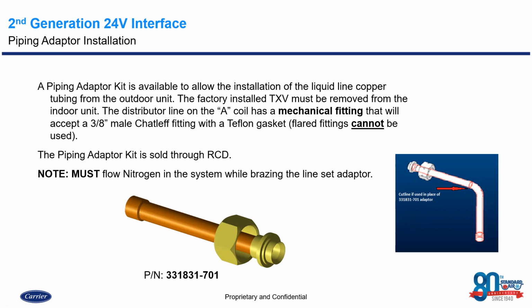Okay, brazing is allowed with this particular joint, and it kind of goes against everything that we've known with ductless thus far. However, when you are brazing on the system, if that's what you so choose to do, you need to make sure that you are flowing nitrogen, at least 1 to 2 psi, just to try to displace any of that oxygen buildup in there, so we're not getting that scaling inside of the pipe, which of course can clog strainers, create restrictions, and cause system operation issues.